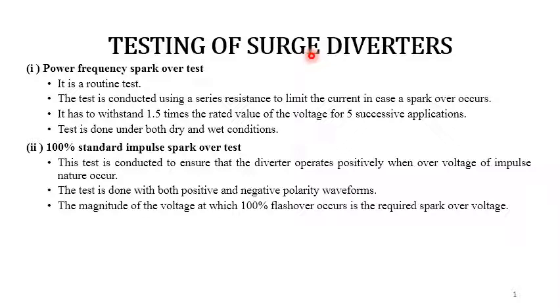So the surge arrester has to be a non-conductor at power frequency voltages. It should behave as a short circuit for transient overvoltages of impulse characteristics, discharge the heavy current, and recover its insulation without allowing the follow-up of the power frequency current. There are different current ratings of the surge diverters that you can see. So we are looking at what tests can be conducted for the surge diverters.